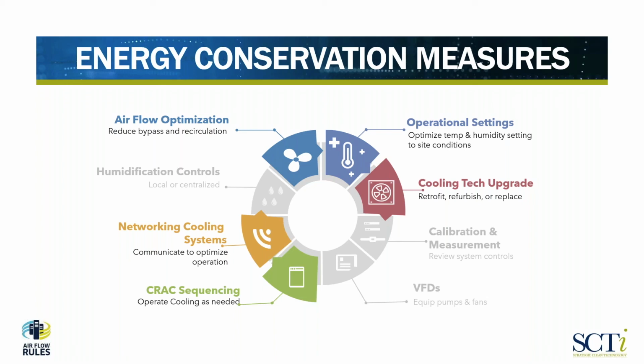Tied in with that, depending upon the vintage of the CRAC units, we look at doing cooling tech upgrades. We've sent out information on our website about what we refer to as a floating head retrofit. That's taking a slightly older version CRAC unit and replacing some of the original components with new components used in the newest CRAC units on the market, making that unit operate more efficiently. We've seen considerable energy savings, and to date we've done over 225 CRAC units with that floating head retrofit, and it's been extremely successful.